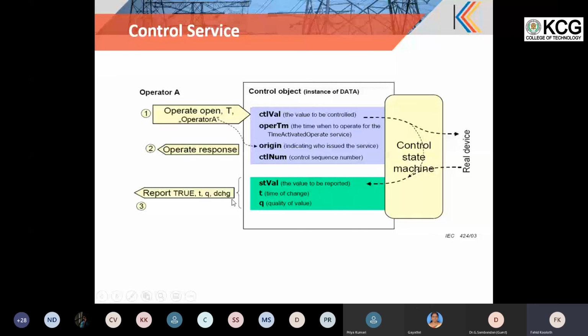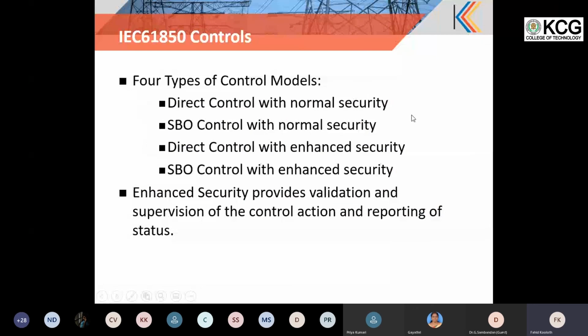So this is control. There are different control models. One is direct control with normal security, that is a client giving a direct circuit breaker open or close command. Second is select before operate control with normal security, meaning a client selects first so that no other client can select, then the selected client can issue a command to operate the device, but with normal security. Direct control with enhanced security means you will get additional feedback, that is a direct operate command, but feedback through the STVAL you are getting back, that is enhanced security. SBO control with enhanced security, select, operate, then followed by feedback you will be getting, that is SBO control with enhanced security. So enhanced security provides additional validation of supervisory control action.